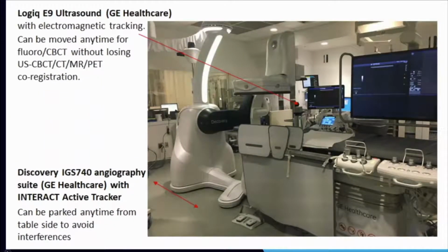This is our setup in the room. We have our Discovery system at the head so it can do cone beams. The ultrasound sits over here, and the screen actually doesn't need to face the operator because it can be displayed up here on the large display. And then you have this very small magnetic receiver that fits over the patient. Moving this C-arm in and out is possible during the procedure. We can move it out when we're using the active tracker for needle placement, and then we can bring it into fluoro over our area, or do a cone beam CT for confirmation, or do the needle guidance updates, which I'll show you in a little bit.